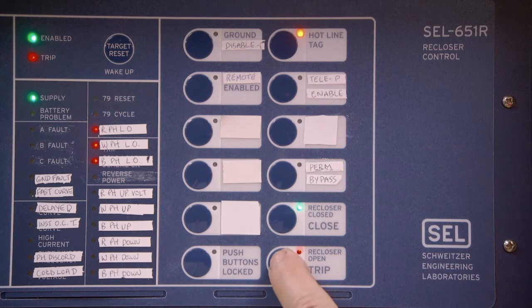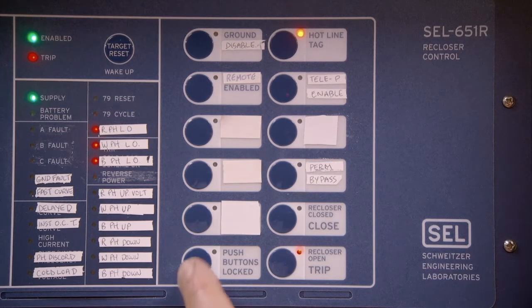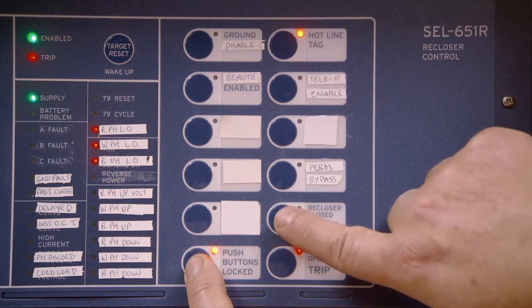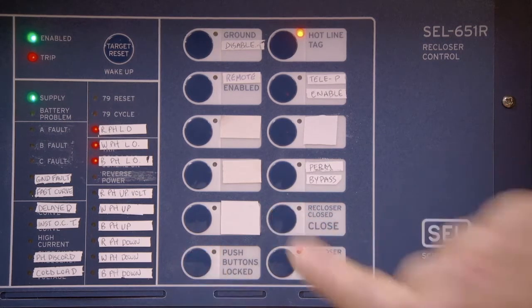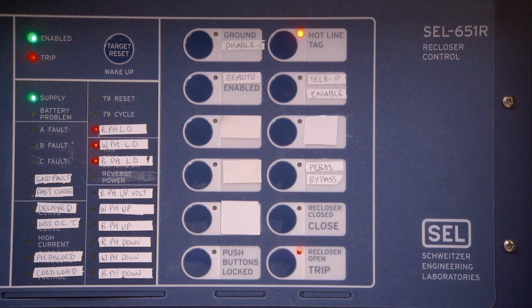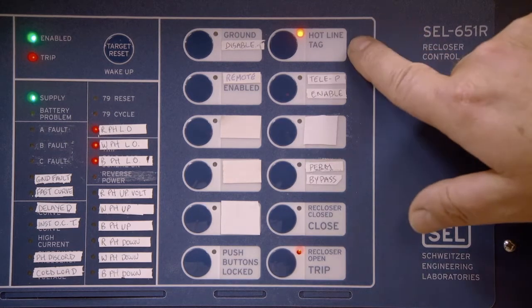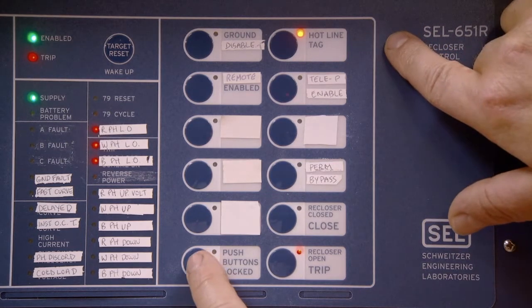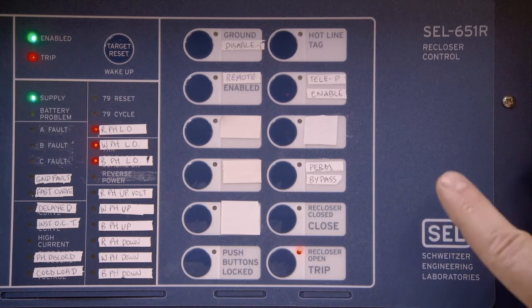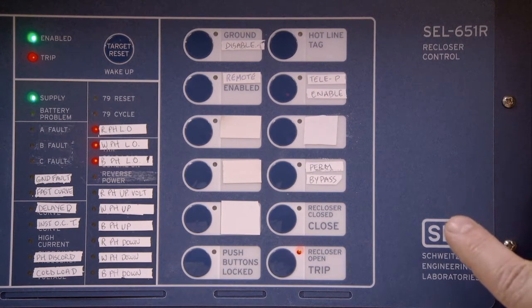Were this to trip out under a hotline tag condition, as demonstrated here, the unit cannot be closed until the hotline tag is removed. This is done by again pressing the push buttons locked and hotline tag buttons simultaneously.